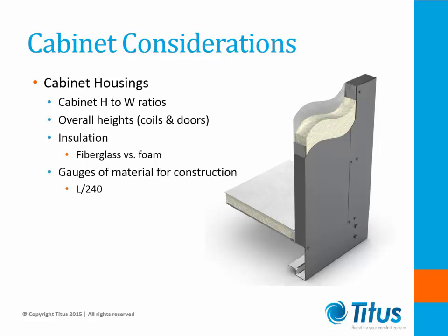The need for focusing more on the L/240 standard comes into play, wherein L is the panel span length and L/240 is the deflection at the panel midpoint. Standards should be written to meet a particular deflection requirement, not just a material thickness. Walls that flex create leaks, and for larger units, deeper walls in thicknesses of 2 and 4 inches may be required to minimize the deflection.